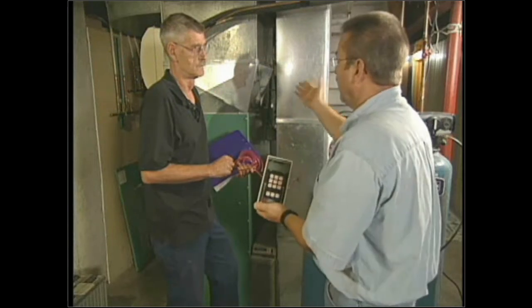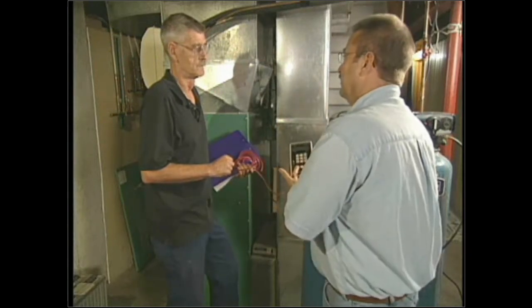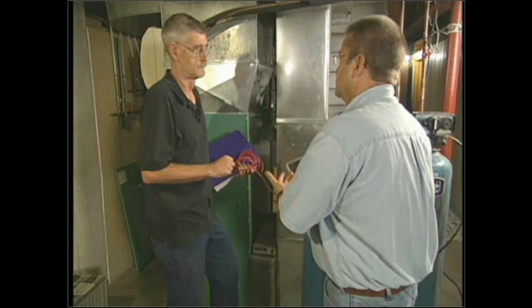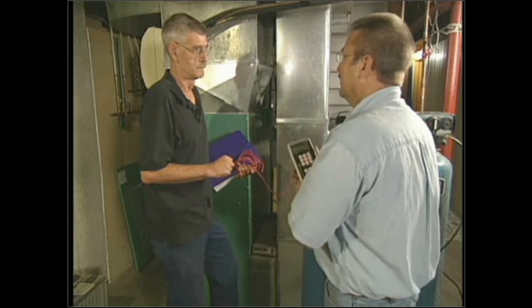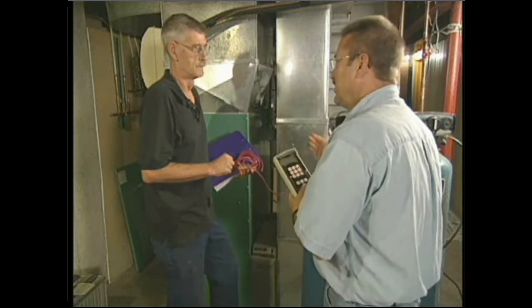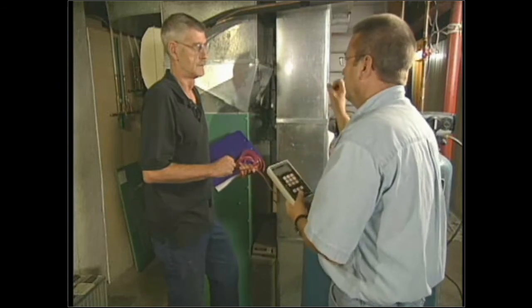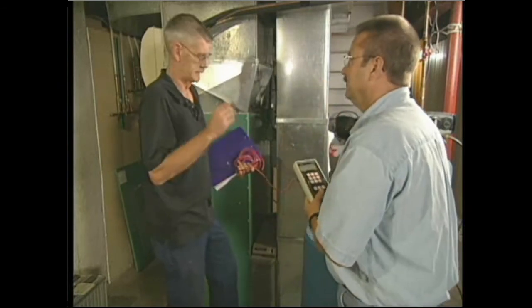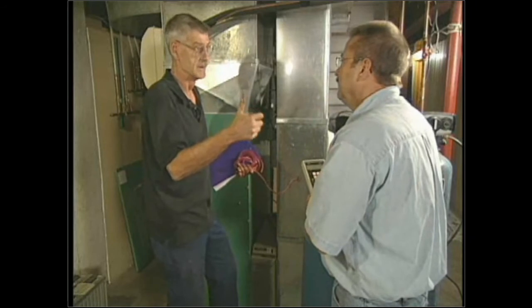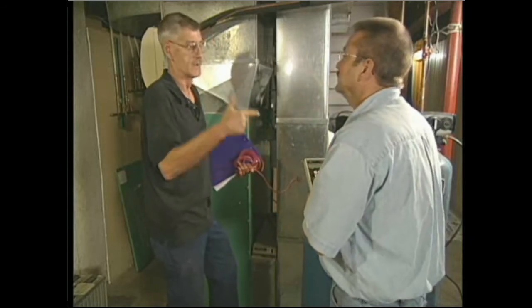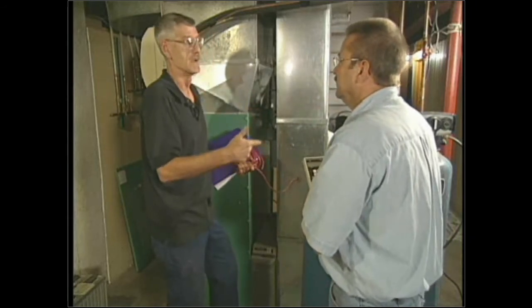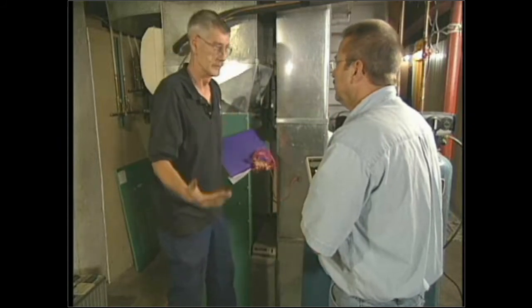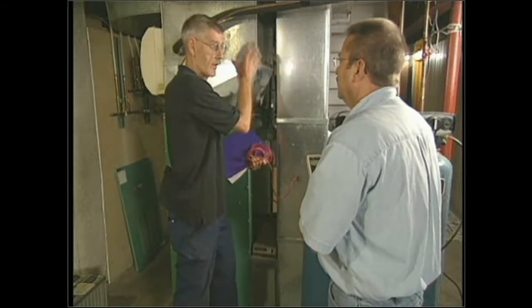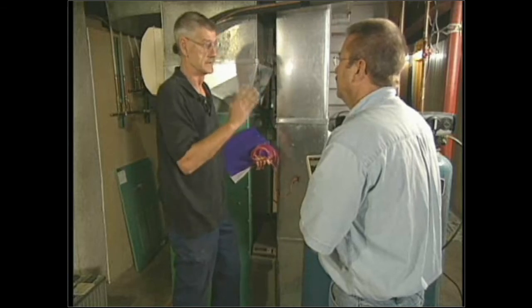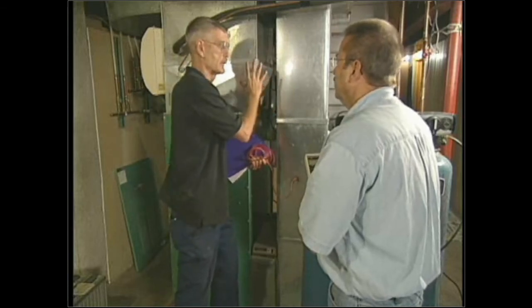So it's a good case in point of how all these tests work together to really give the homeowner the best possible system, because you're documenting all the results and making recommendations so the contractor can read these, come in, and perform all the different adjustments. And at the end, the homeowner's going to have the most efficient operating system possible. The system will be at its highest SSE. The system will have the proper airflow. It'll have the proper static pressures. So everything works as one unit, and it allows us to tie it all together. All this testing is just so we get the homeowner the most optimum performance out of this heating system that we can.